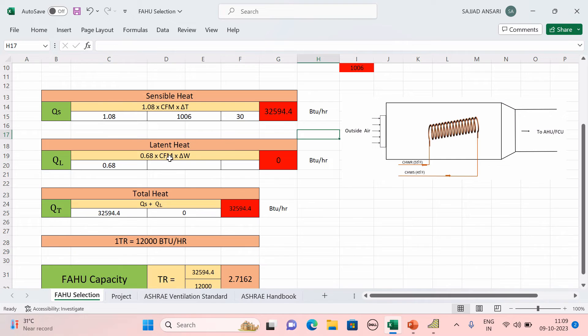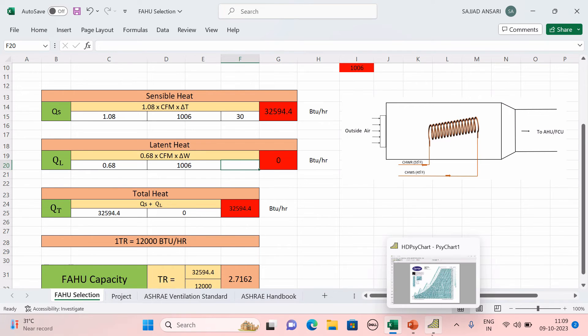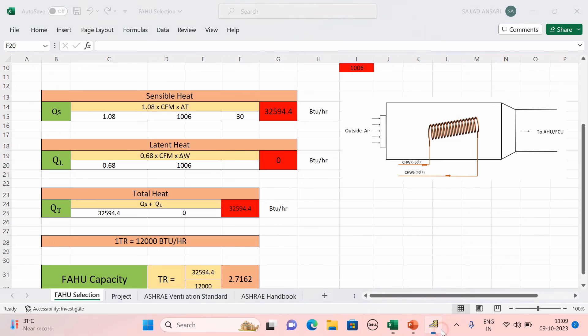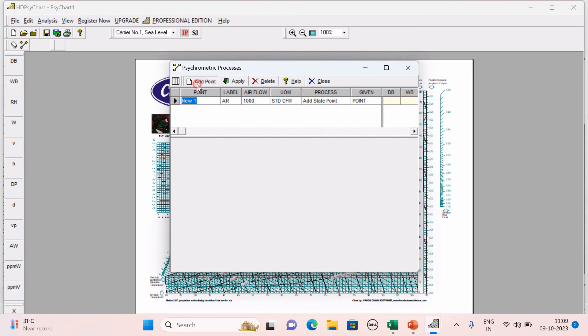Now calculate the latent heat using the formula: 0.68 × CFM × ΔW. CFM is 1006. Delta W is the change in humidity ratio. To find humidity ratio, I am opening a psychrometric software. Click 'State Point and Processes', add point, and write the city name — Hyderabad. Enter two properties of air to get the remaining properties.